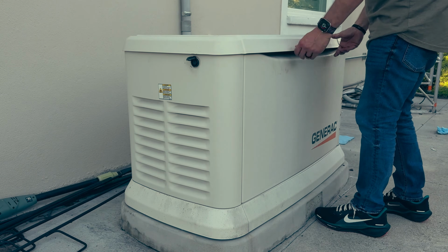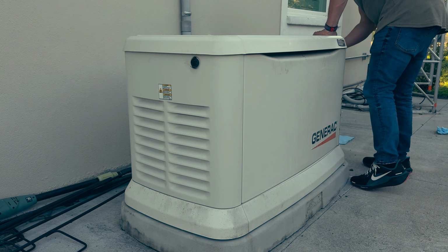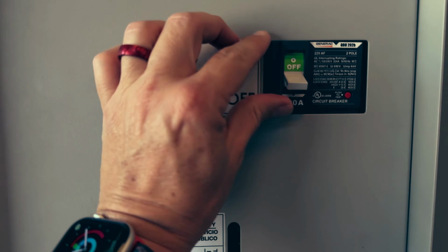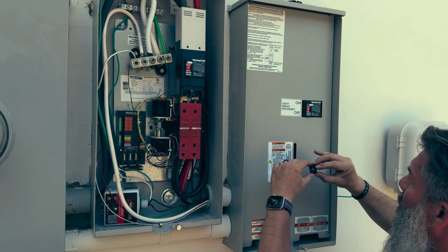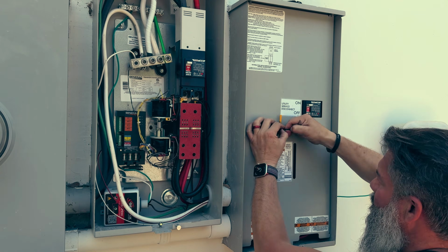Head inside and check to see if your lights are back on, and if so, let's secure everything and finish up. Now that the house is powered, close the generator lid and lock it. Double check the ATS main breaker, and if it's still off, turn it on. This tells the generator when utility power is restored, so it doesn't keep running when it doesn't need to.